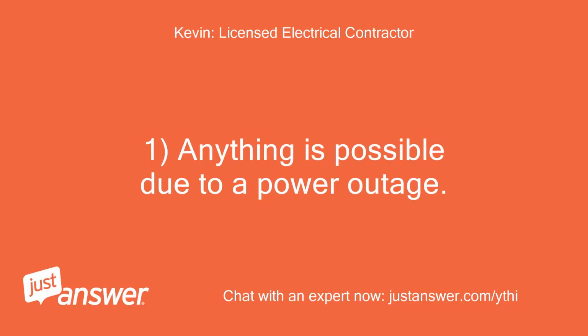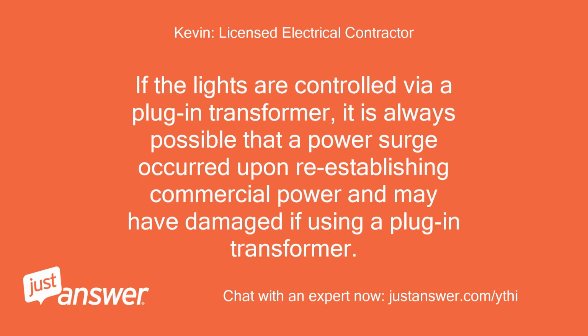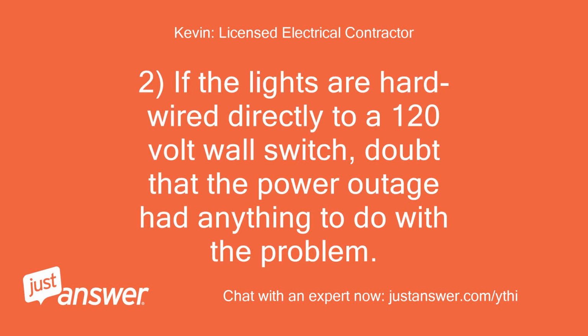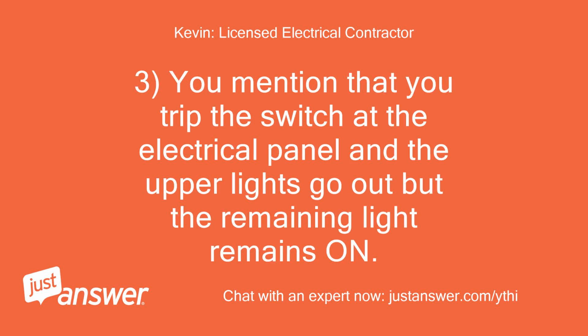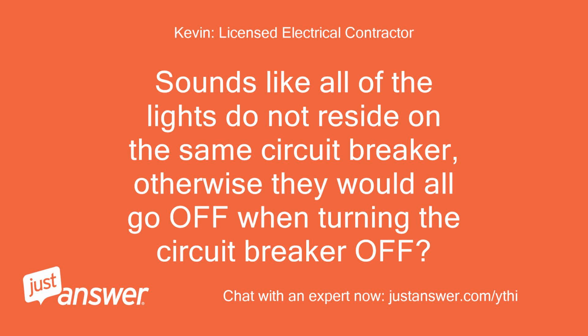1. Anything is possible due to a power outage. If the lights are controlled via a plug-in transformer, it is always possible that a power surge occurred upon re-establishing commercial power and may have damaged it. 2. If the lights are hardwired directly to a 120-volt wall switch, I doubt that the power outage had anything to do with the problem. 3. You mentioned that you trip the switch at the electrical panel and the upper lights go out but the remaining light remains on. Sounds like all of the lights do not reside on the same circuit breaker, otherwise they would all go off when turning the circuit breaker off.